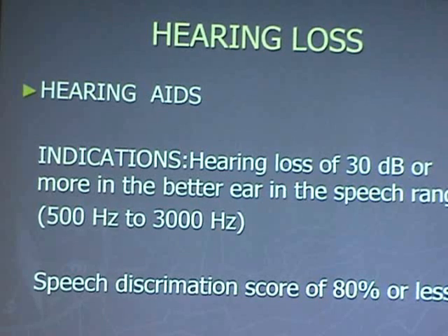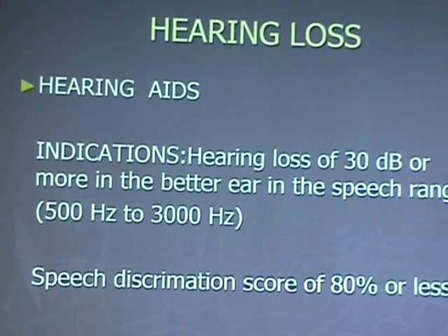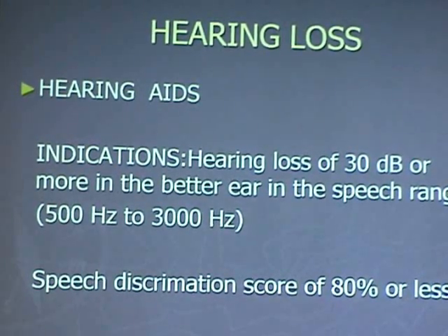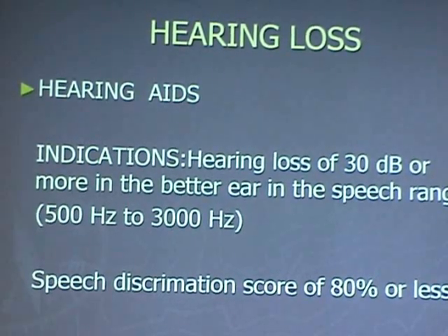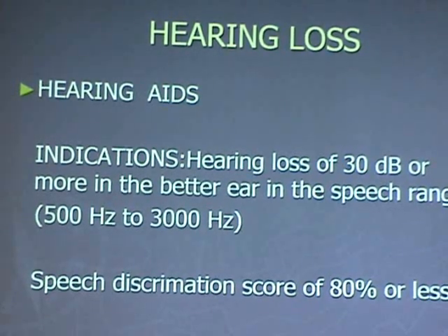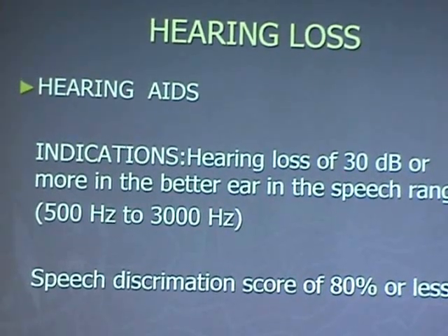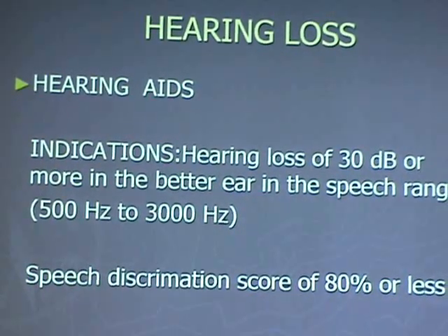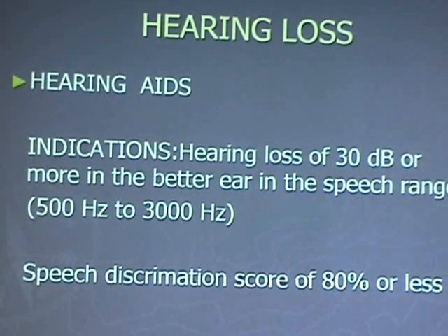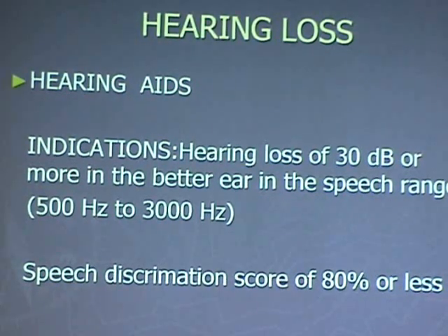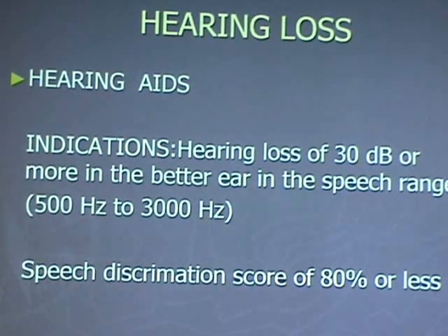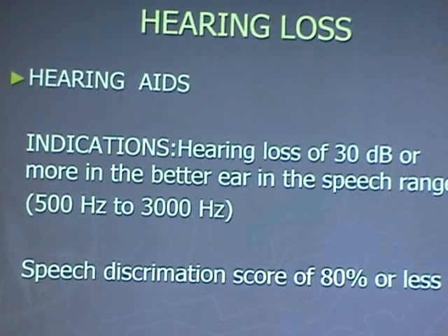Hearing aids have really changed in the last few years, really changed. They have become more than something that just amplifies all sounds; they are very selective of what sounds they do amplify. And these new digital aids can adjust each frequency for how much loudness you want in that frequency, or turn some of them completely off. So if you have a hearing loss in certain frequencies and the other frequencies are normal, they can adjust that aid just for the frequencies you need amplification, without going into the other frequencies.